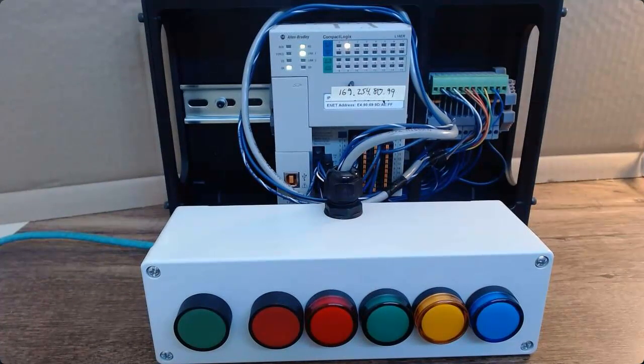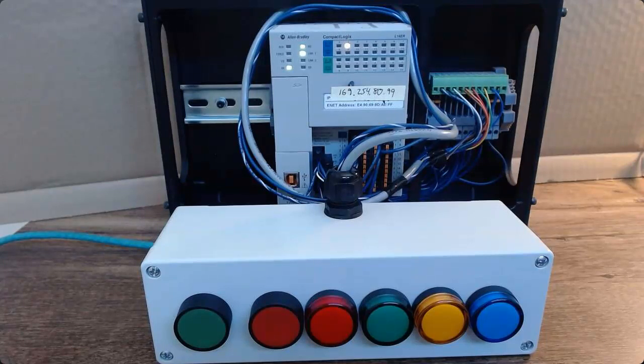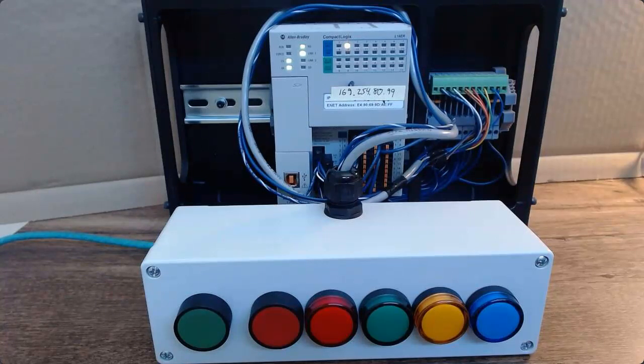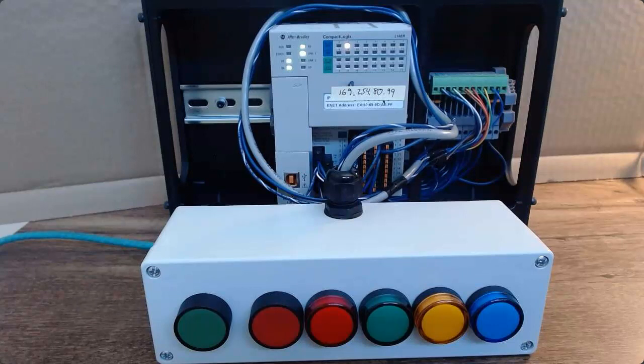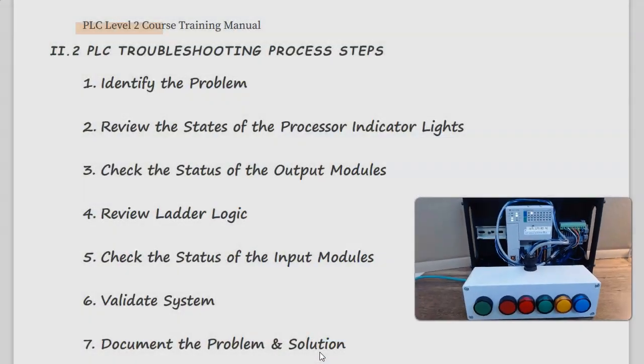Now this simulates what could happen in an actual installation if we have an expansion IO module go bad. In other words, the PLC cannot find it based on the configuration, and it therefore would give us a configuration error.